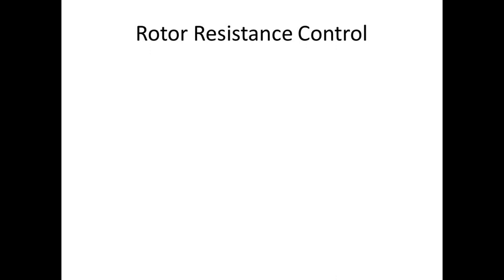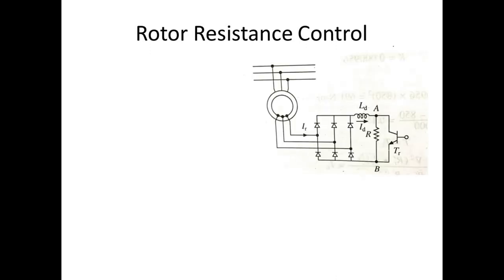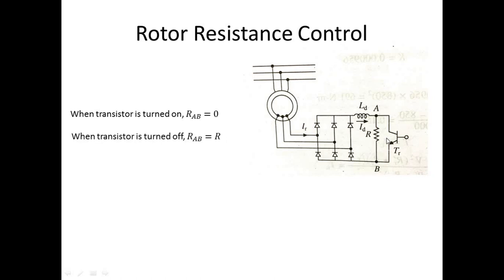To control this resistance in a stepwise manner, we use a power electronic circuit. We convert the three-phase rotor circuit using a diode rectifier to DC, and connect a resistance here. A power electronic switch is placed in parallel with the resistance. When the switch is turned on, the resistance across it equals zero; when the switch is turned off, the resistance equals R.